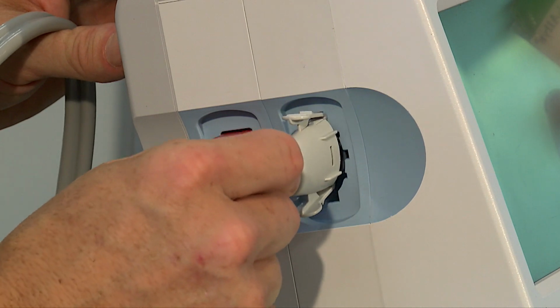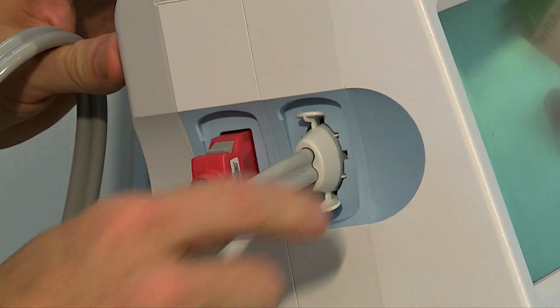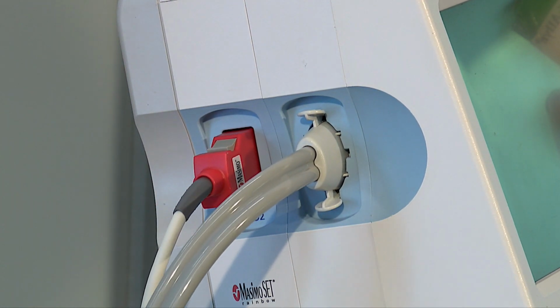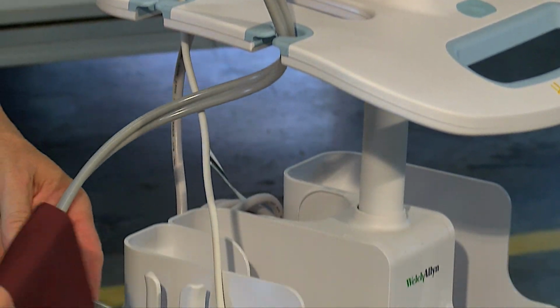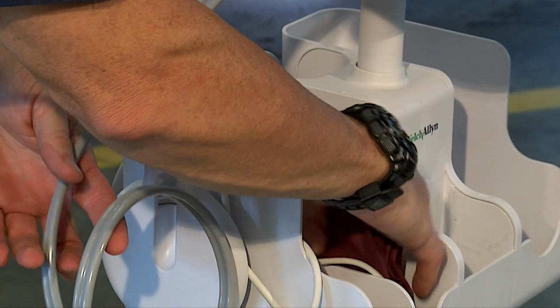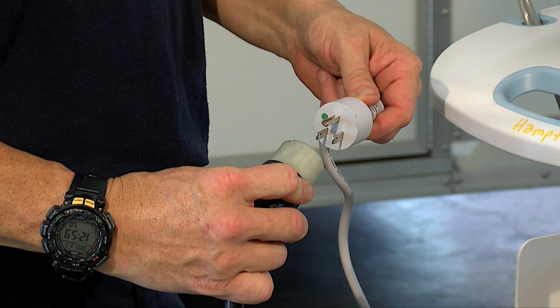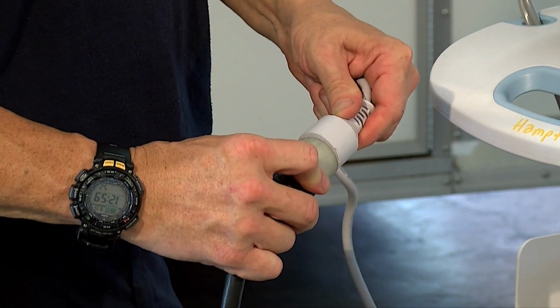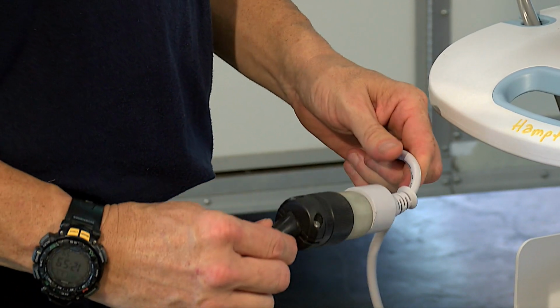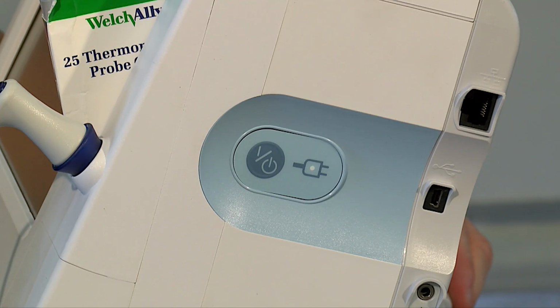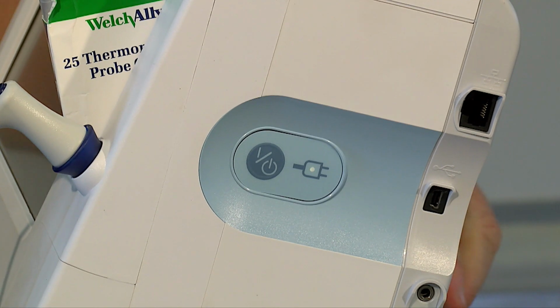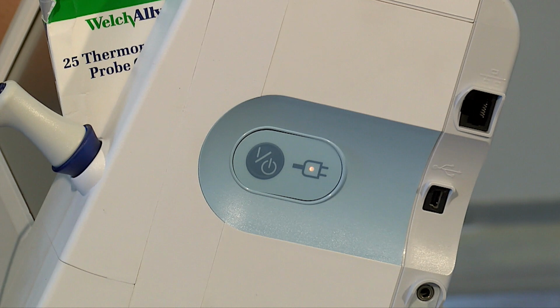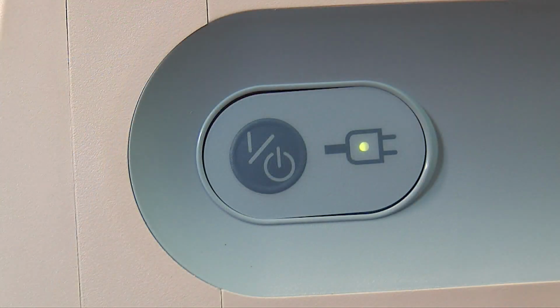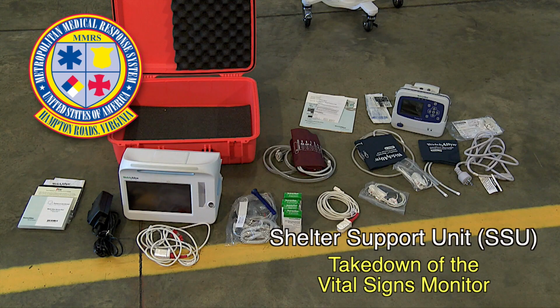The BP cuff is plugged into the slot next to the SPO2 plug on the left side of the monitor. The extra cord can be slid through the slot on the monitor's mount and placed in the side tray. At this point, it is important to plug the monitor into a power supply so it can begin to charge the internal battery. When the monitor is plugged into a power supply, you will see the indicator light illuminate next to the monitor's power switch. The light will illuminate amber when charging and green when fully charged.